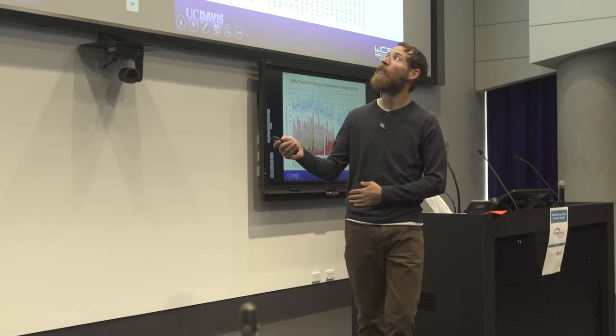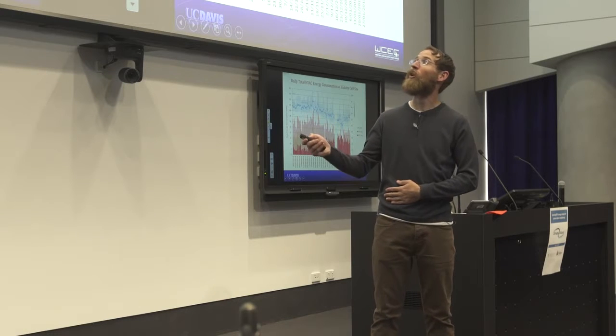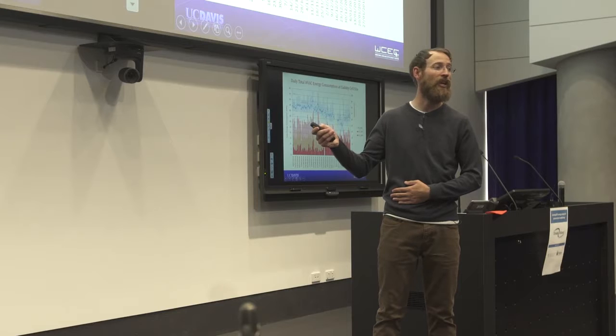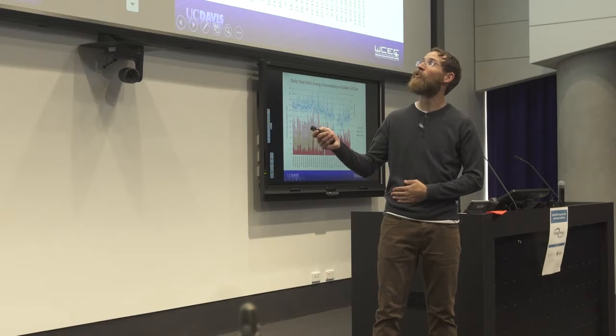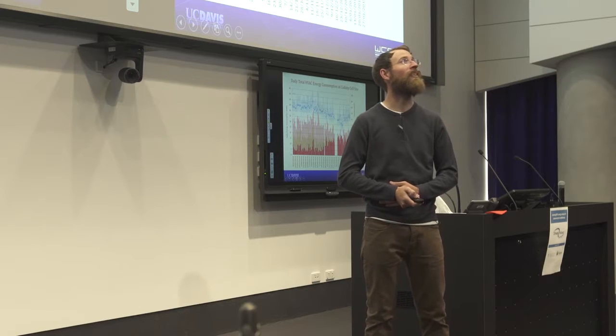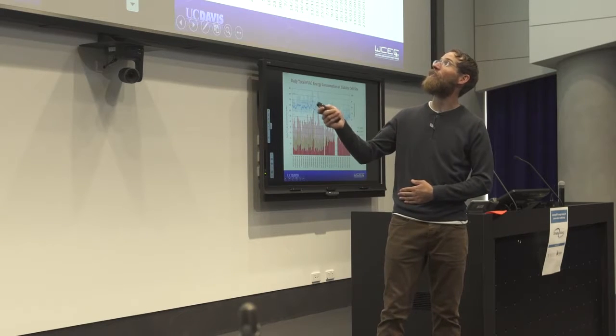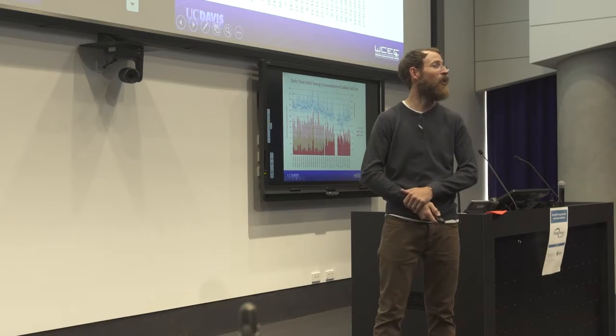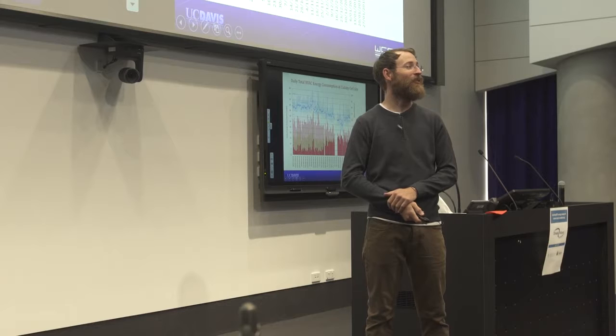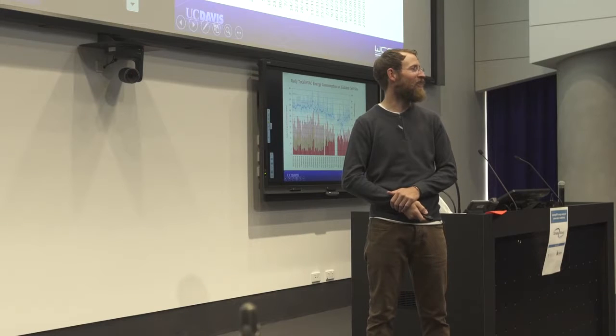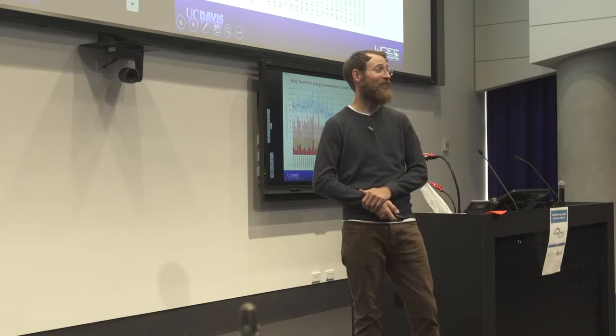And so this chart shows the daily energy consumption recorded. Each bar represents the total energy consumed in each day. The red bars represent the amount of energy consumed by the compressor-based systems, and the green bars show the amount of energy consumed by the indirect evaporative cooler. So this is over the course of several weeks. The blue dots show the average daily temperature, and the extremes, the high and low for those days. And so you can see a very clear trend emerging here. Obviously, the days with indirect evaporative cooling use quite a bit less energy than the days without. In fact, it's between 40 and 70% less energy, which is really quite exciting to see.